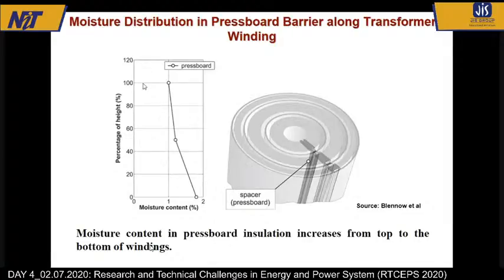This study shows the moisture distribution from 100% height, that means the top, to 0%. At the top, it is around 1%. At the bottom, it is around 1.8 or 2%. This is for a particular transformer. Now, here again, there is another practical piece of information we have to go through: in a transformer, since its height is maybe 2 meters or more, is the temperature the same at the top and the bottom? The answer is no.